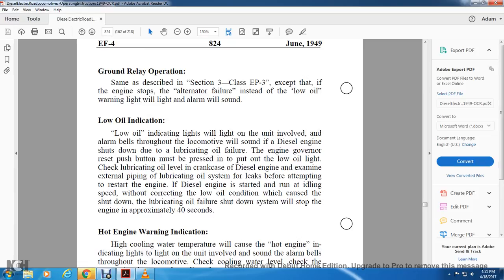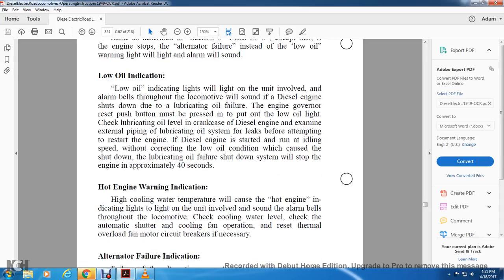Check the lubrication oil level in the crankcase of each engine. Examine the external piping of the lubricating oil system for leaks before attempting to restart the engine. If the diesel engine is started and run at idle speed without correcting the low oil condition, the lubrication oil failure shutdown system should stop the engine in approximately 40 seconds.